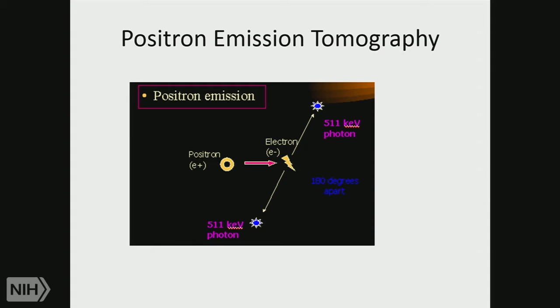So that's much better, well, it's twice as good as the SPECT emitter that only produces one gamma ray per decay. You get two, but you get directionality out of it, because you know that if you're hearing it here and one over there, the event happens somewhere along this line of response. So PET scans are highly sensitive, provide metabolic information, and have much better spatial resolution than SPECT because of this feature. You don't need to collimate them because you're only going to accept the events that occur simultaneously. So you get much more efficiency with regard to how much radiation the patient has to get to how much imaging you need. So you can lower the dose.